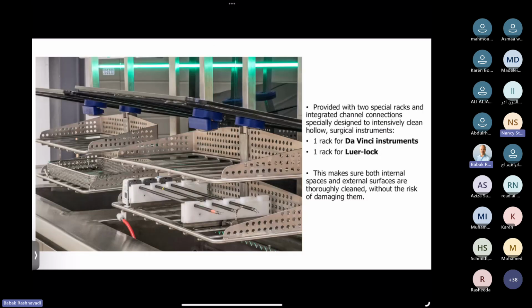Okay, so here you can see when it's open, we have 2 levels. Those 2 levels on the left side are the pre-rinsing sink. You put all your heavy duty trays in that, like orthopedics and so on. It will go down and spray all the dirt away. From that stage you go to the right side, and you put your trays also on those 2 levels, and then you have the ultrasonic cleaning. We also have this specific tray to clean Da Vinci, or any other robotic instrument is possible. And we also have a special rack to connect with the luer lock all kinds of hollow instruments. Next, please.